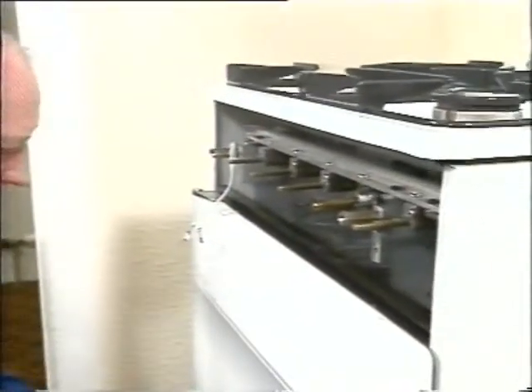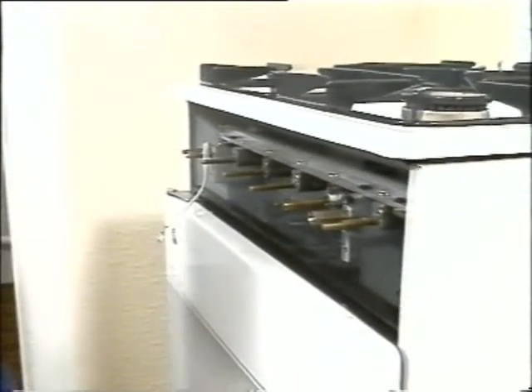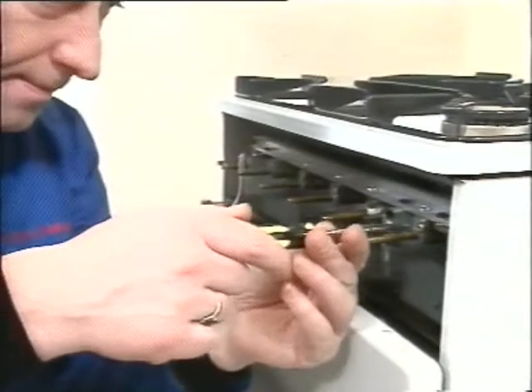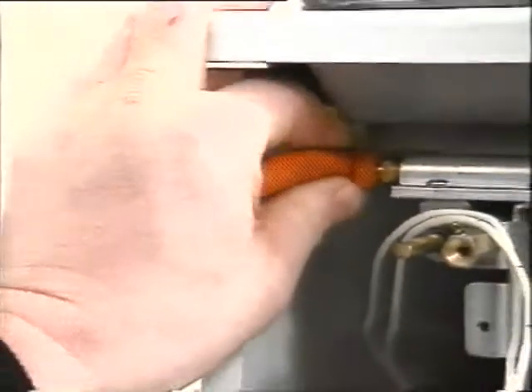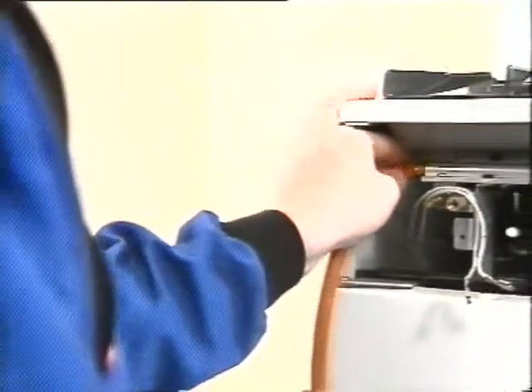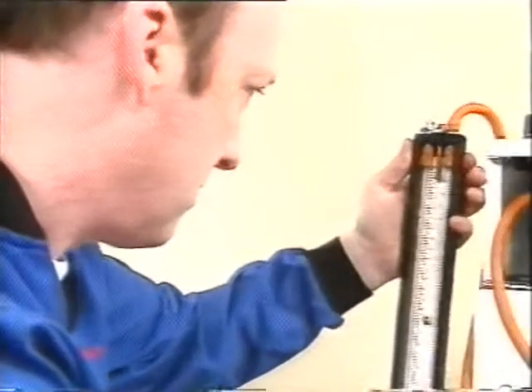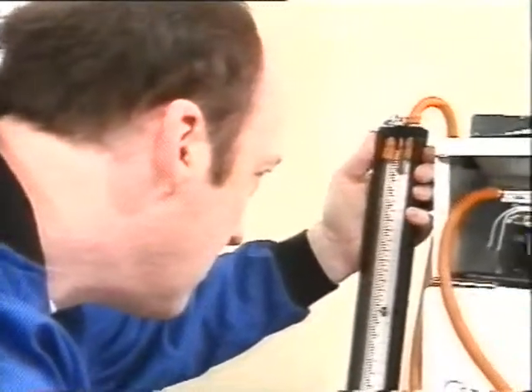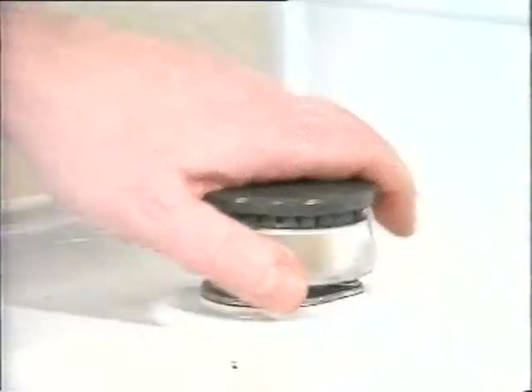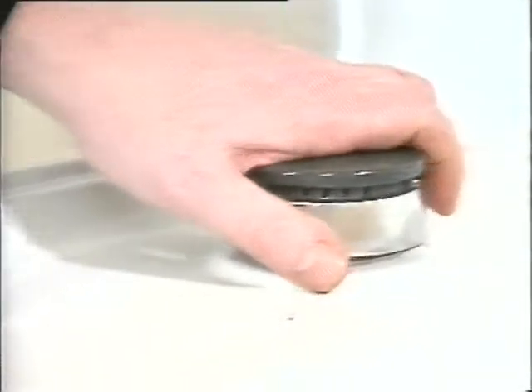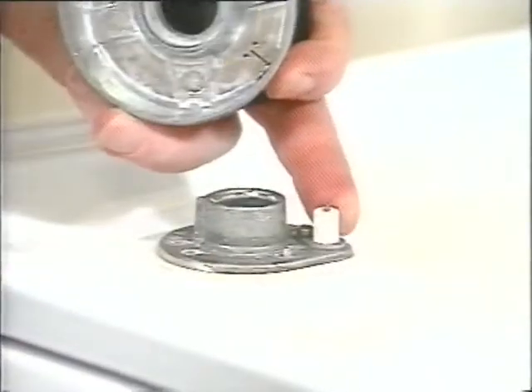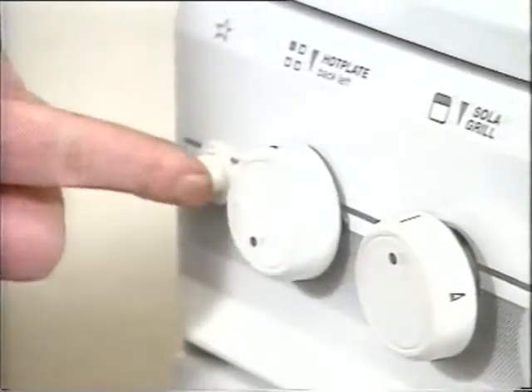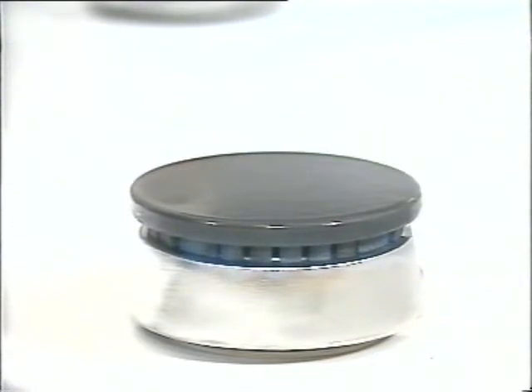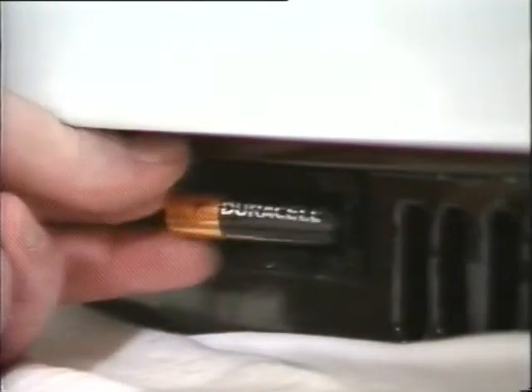First, check all the taps, and after disconnecting them from the gas supply, ease and grease them if they need it. Once the appliance has been reconnected to the gas supply, make sure that the appliance pressure's correct, and if a governor's fitted, for example, as in an LPG appliance, check that it's clean and level. Now look at the whole ignition system. Check that all the ignition devices and electrodes are clean, and that the ceramics and insulation are in good order. Test the ignition to make sure it's satisfactory. Then finally, if there's a battery, check its condition.